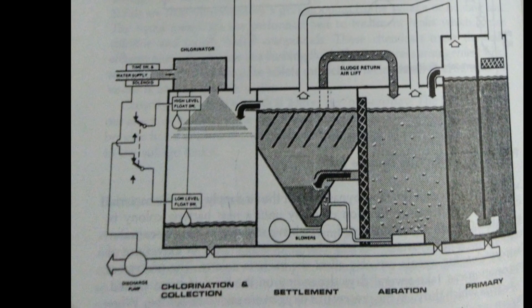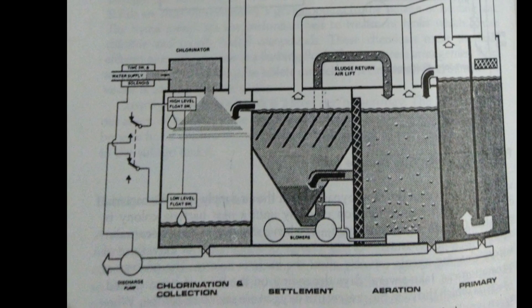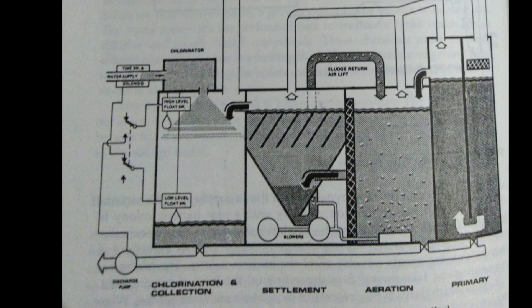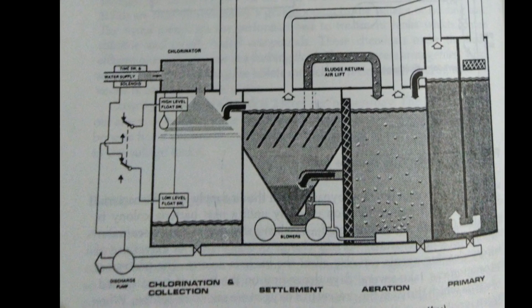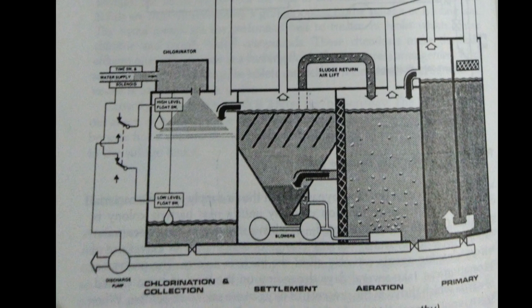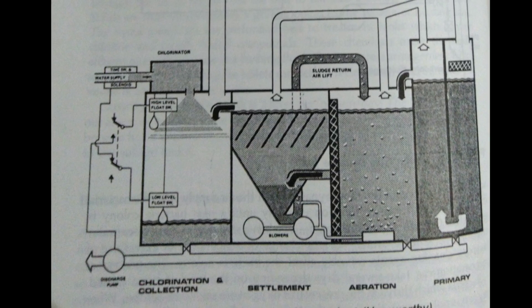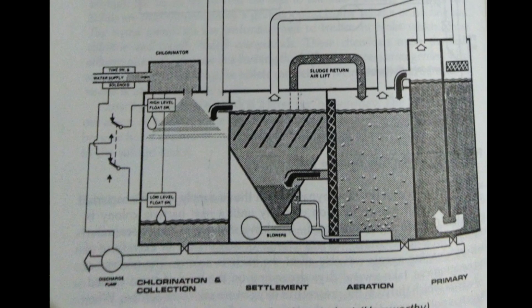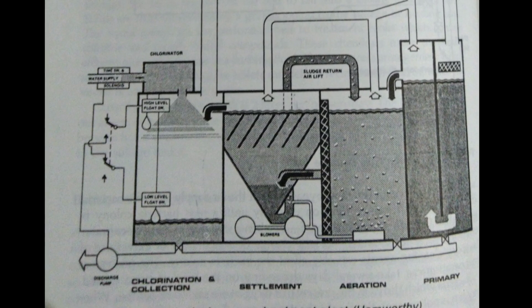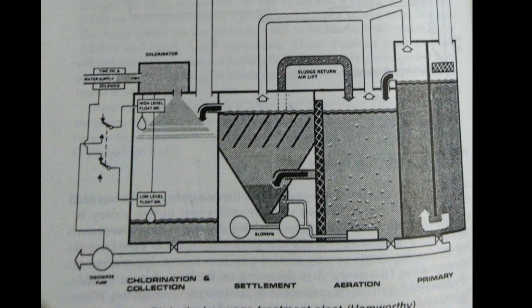The theory is very simple. Most marine sewage treatment plants will have three stages. First, it enters through a mesh-like screen that breaks waste down into smaller particles, or there are blades or an impeller that turn when waste falls on them. Then it goes through the aerobic or aeration stage. After that comes the settling stage, and after settling it circulates back to the first aeration stage. The air keeps circulating, and sometimes you will see transparent pipes on top where this circulation takes place.